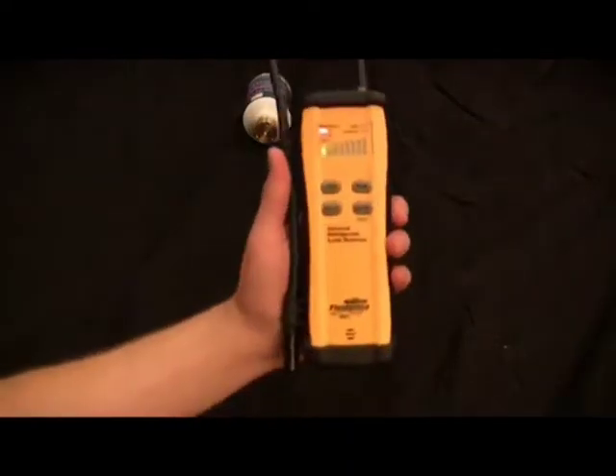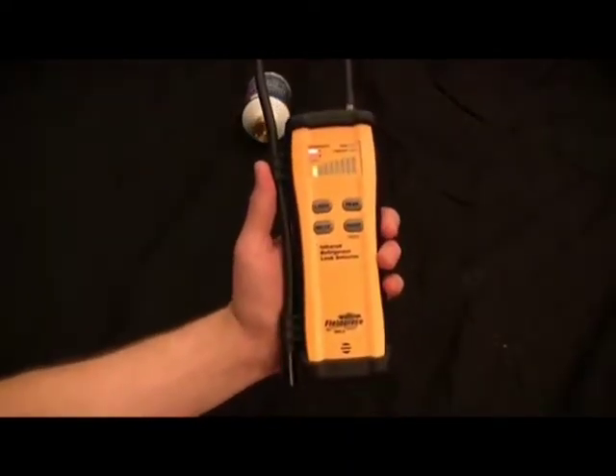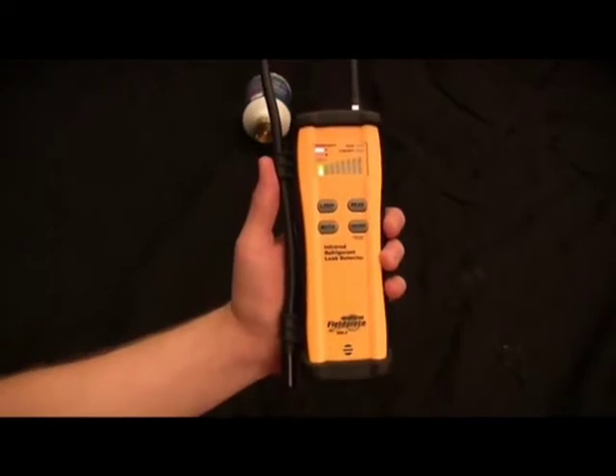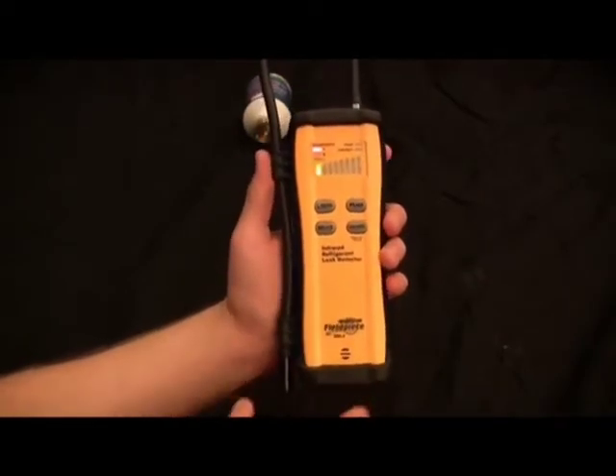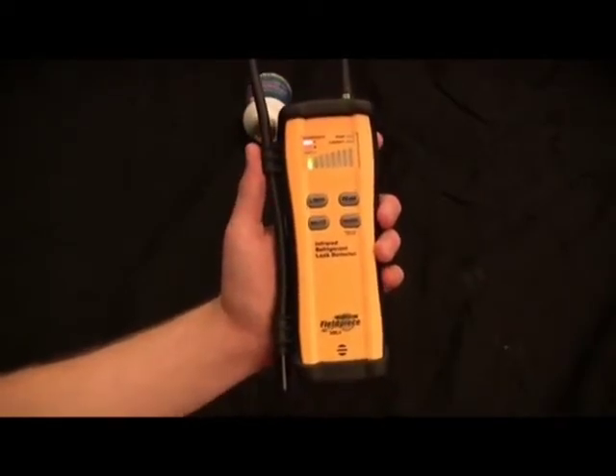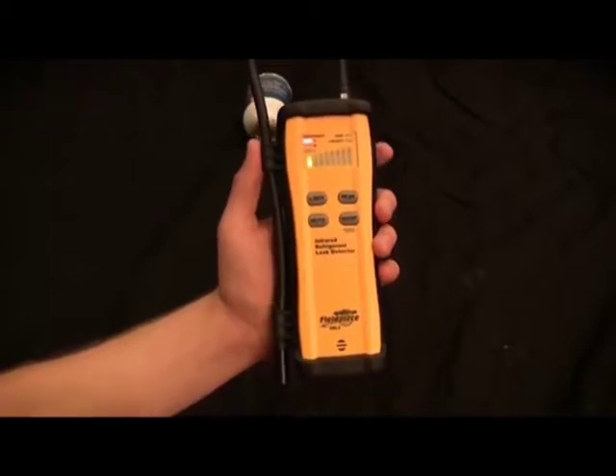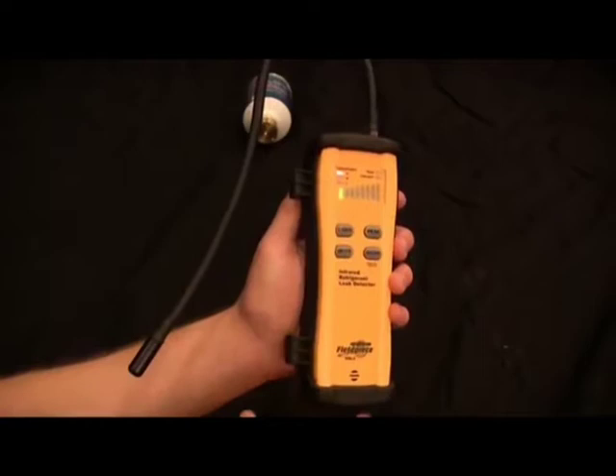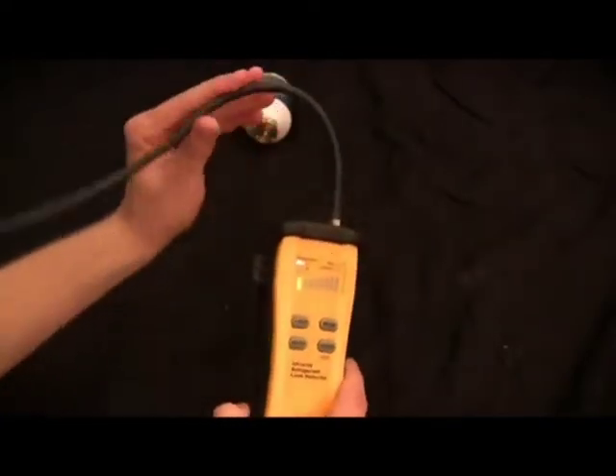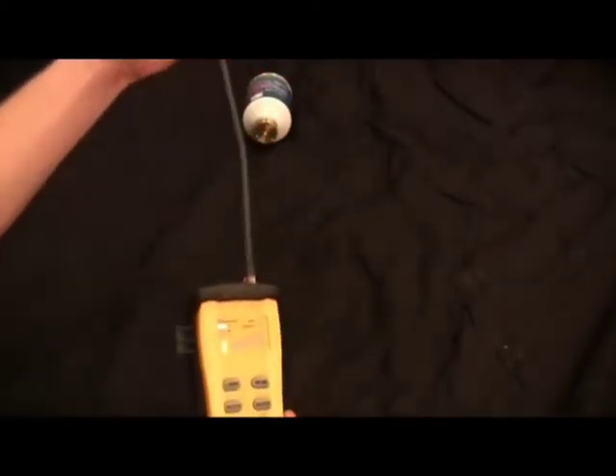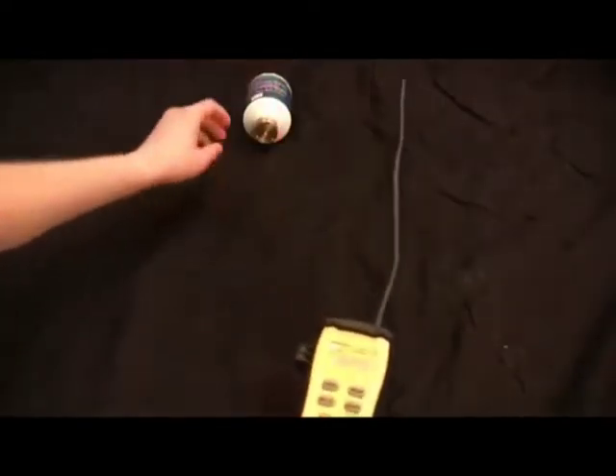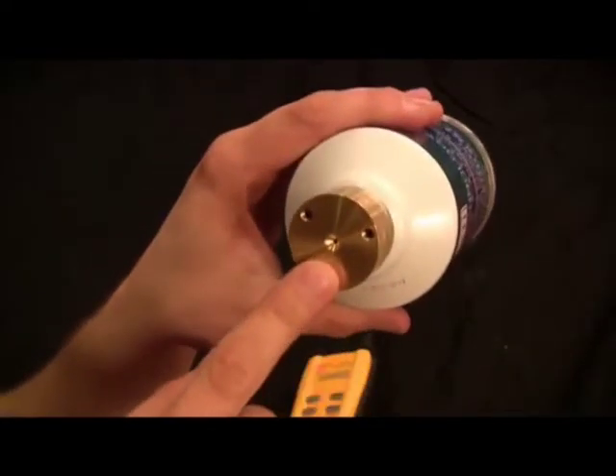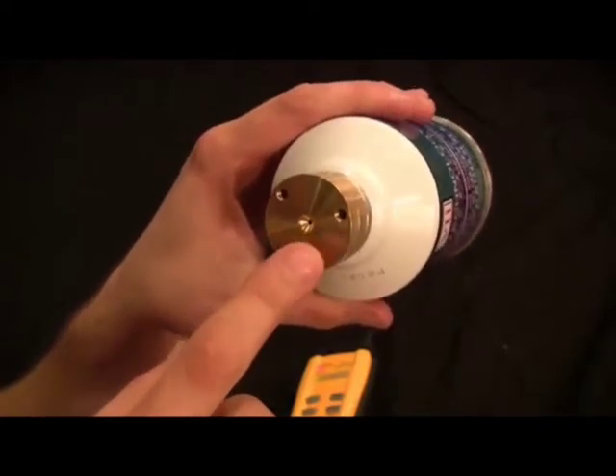So the leak standard right here that I have, you can see that it has a hole and it's just replicating a 0.31 ounces per year outside of that hole. And so let's show you how it works in action. So what you want to do is just slowly move it across the leak and sweep it by and you'll see that it goes off. Now as it goes off, you want to pass it and keep moving and then sweep back and it will go off again as you keep on passing the leak.